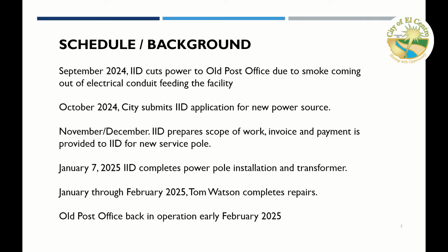Upon investigation, it was determined that the electrical system was beyond repair and needed to be gutted and replaced—everything from and including the IID power pole, the conduits coming down from the transformer in the alley, down into the main electrical switch gears, and everything going into the basement of the structure, including the equipment in the basement. All of that was repaired and replaced.